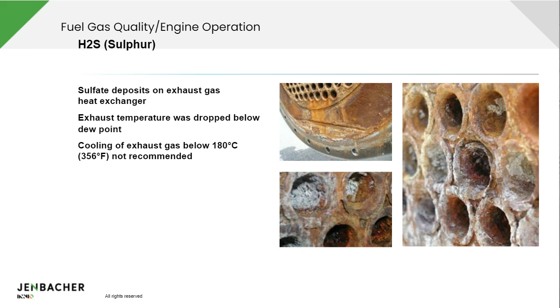So these exhaust heat exchangers, if they do experience condensate or high sulfur, they will extremely quickly wear and then need to be replaced, which can be a considerable maintenance cost. So that's one thing to consider. One option also would be obviously to not have an exhaust heat exchanger in the first place, but then you reduce your total recoverable heat from the engine. So exhaust heat exchangers are quite common for these types of applications, and you just have to make sure your gas is clean and doesn't have much H2S in it.